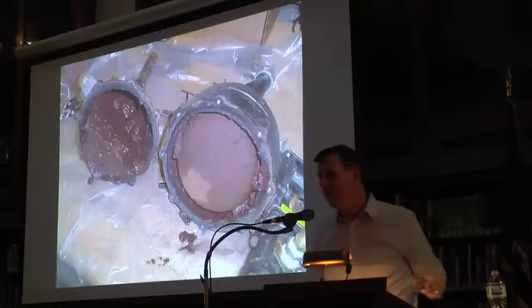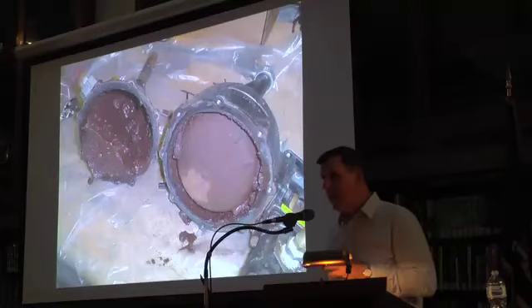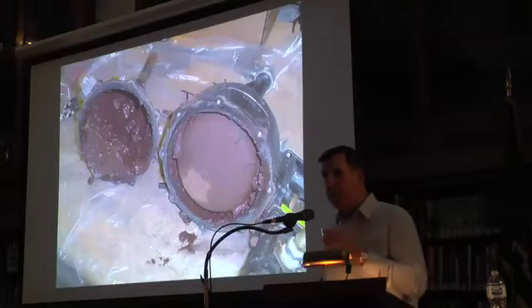This was an insurance photograph sent to me by McDonald Miller. The building burned down, and they went in and they found a low-water cutoff, and they said it was never blown down.